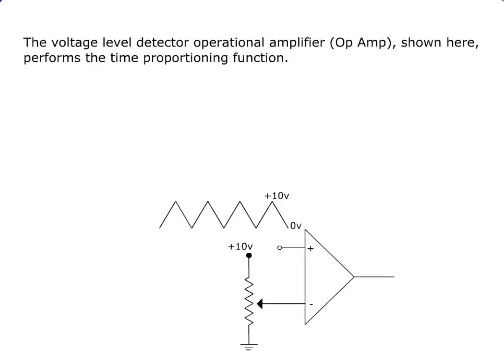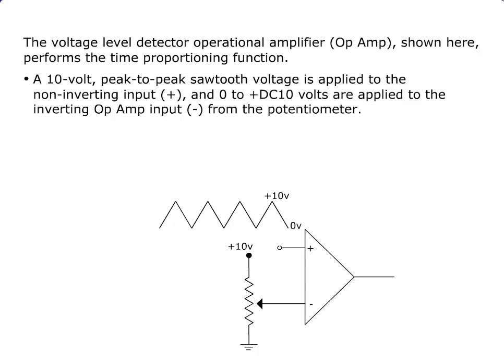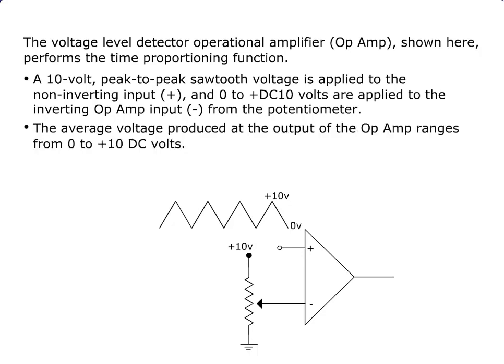The voltage level detector operational amplifier, or op amp, shown here, performs the time proportioning function. A 10 volt peak-to-peak sawtooth voltage is applied to the non-inverting input (positive), and 0 to DC 10 volts are applied to the inverting op amp input (negative) from the potentiometer.